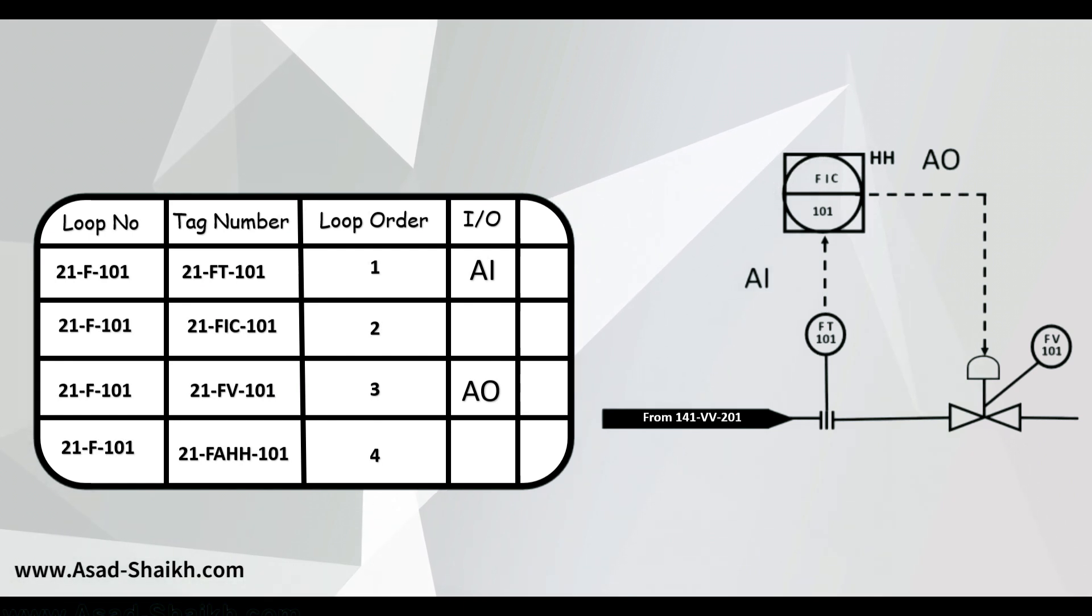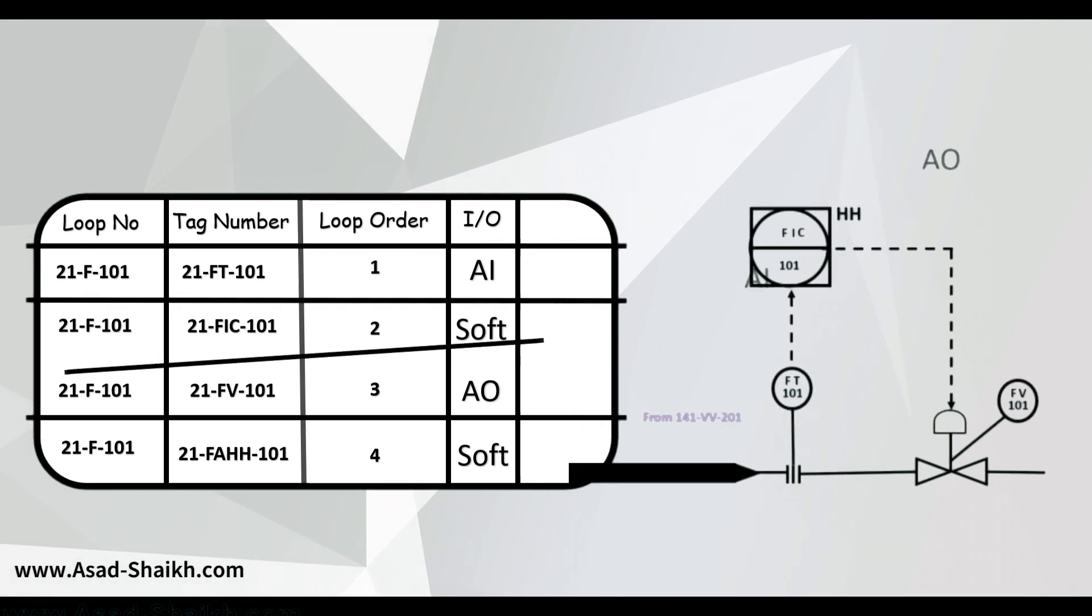But what about the FIC? FIC stands for flow indicating controller. So if you see here this is a soft signal. Why? Because neither is something coming inside the control system nor something is going outside. So if you see for example here this happens within the DCS itself which is going to indicate on the display. Hence it is a soft signal. The alarms are also being generated inside the DCS. Again they are soft signals. There is nothing entering or exiting the system. This is the basis to purchase your control system.